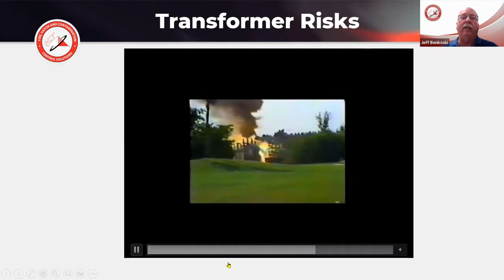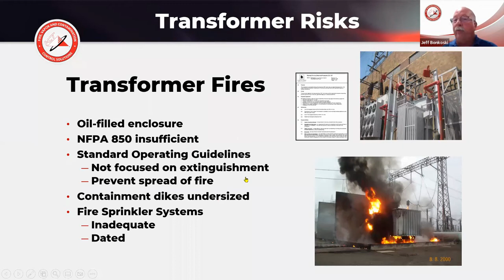And how many times do we see, with lightning strikes, or just because of the energy usage, overloading these systems, causing these transformers to overheat, fail and catch on fire? They're filled with oil, they're getting older, and sprinkler systems, we saw, do not work on three-dimensional fires, especially when we're dealing with a flammable liquid. When we look at a substation here in New York, foam and dry powders were used trying to extinguish this. Didn't work.